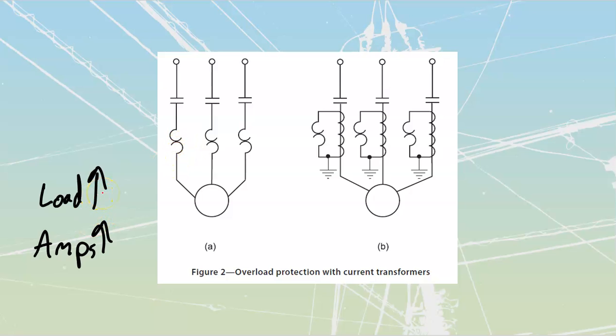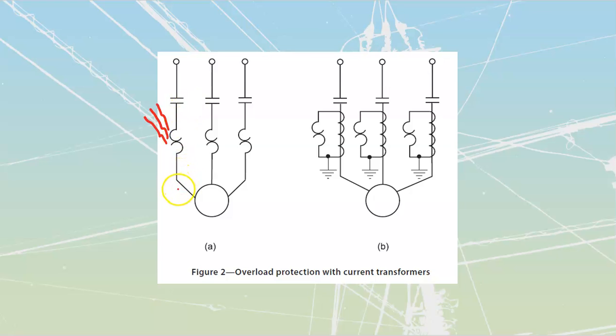Well, we haven't created them. We've used them. Smart people other than us have built them. But these overloads are simply going to be little heaters that are placed inside of each line going to the motor. Okay? And so these little heaters are going to pass current through. They're not going to generate a ton of heat because we don't want to be dropping a lot of watts off of our system. But they're going to generate a tiny little bit of heat that is going to get applied to either a solder pot or a bimetallic strip. We'll use the example of a bimetallic strip.